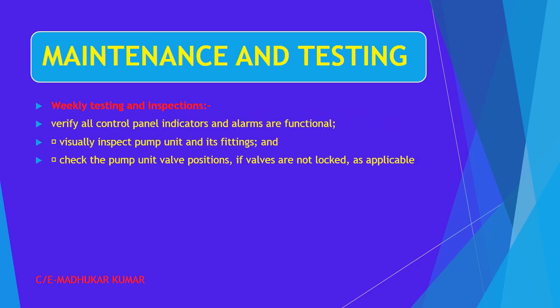Now we are going to see the maintenance and testing part. First, weekly testing and inspections. We have to verify that all the control panel indicators and alarms are functional. Visually inspect the pump unit and its fittings. Check the pump unit valve positions, that valves are not blocked, as applicable. A visual inspection of the complete system has to be done on a weekly basis, covering all the fittings, all the valves and all the pump control panel indicators.